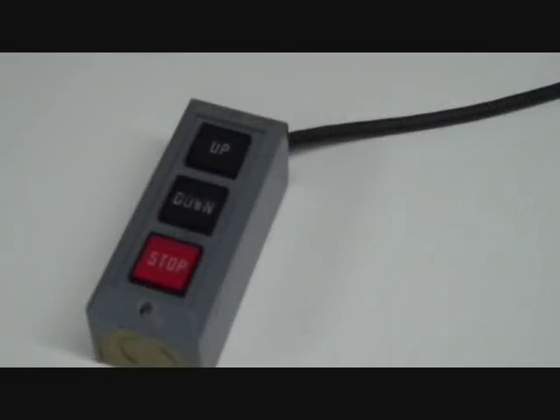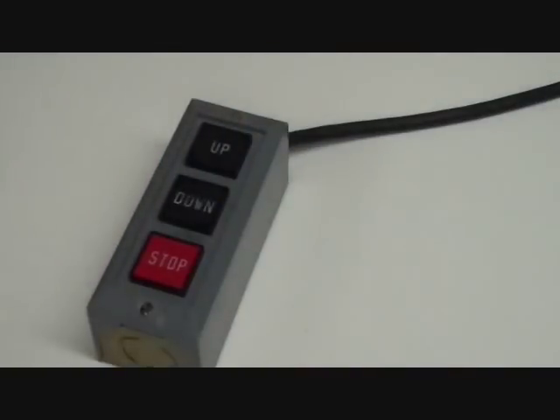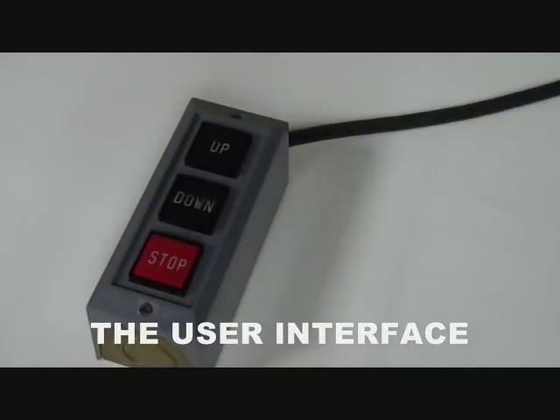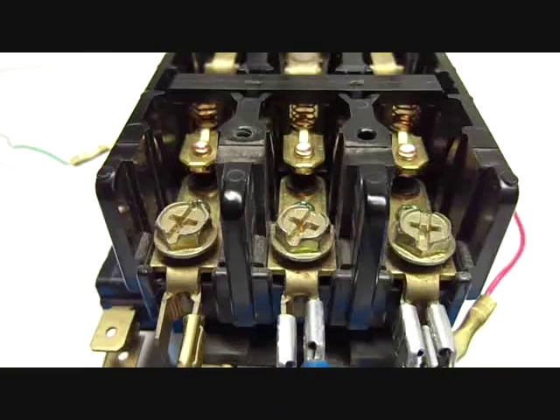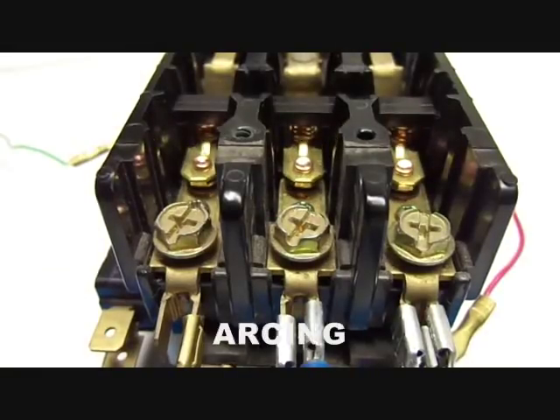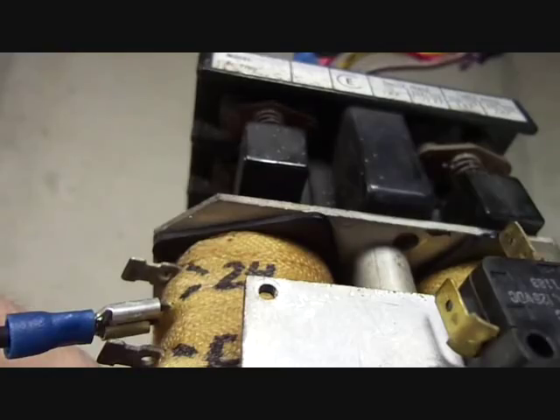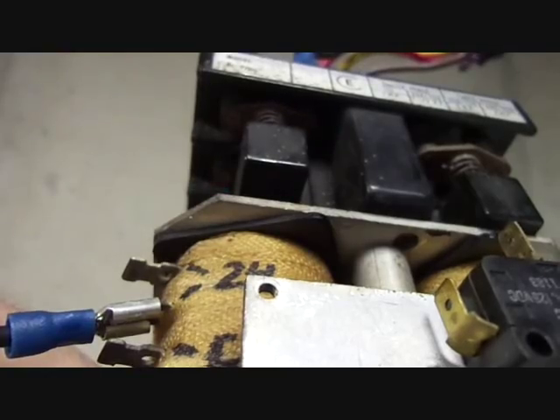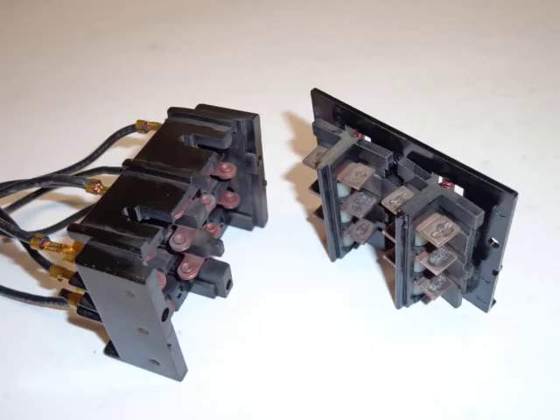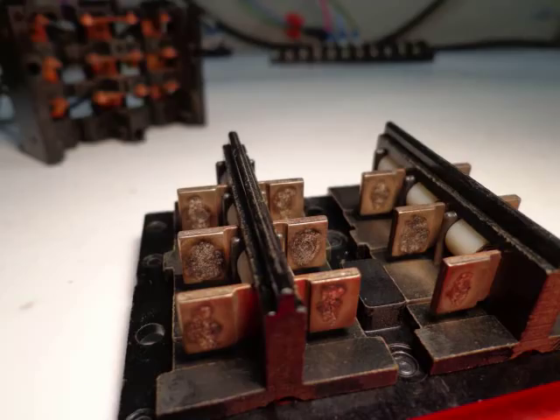Another reason is safety. You don't necessarily want 230 or 460 volts running through the user interface where it could short out and electrify the enclosure. And when it comes to industrial motors, you need a reliable, fast-acting switching device to minimize arcing. When these contacts get within about a millimeter of each other, the current will jump from one contact to the other, and that develops a lot of heat, which will eventually ruin the contact surfaces. So the faster you can engage the contacts, the less time they spend arcing.